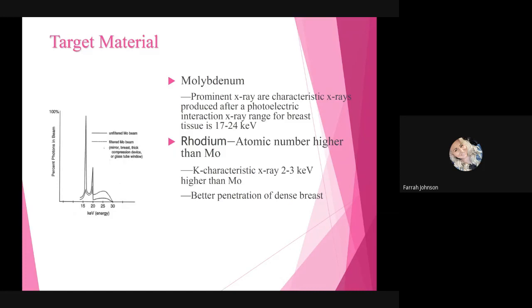So then that brings us to target material. In mammography, the typical target material is going to be molybdenum. This is because the prominent X-rays are characteristic X-rays produced after a photoelectric interaction, and the X-ray range for breast tissue is going to be anywhere from 17 to 24 keV. You can also use rhodium targets. The atomic number is slightly higher than molybdenum, and it has a K characteristic X-ray of 2 to 3 keV higher than molybdenum. Rhodium is helpful when trying to better penetrate dense breast tissue.